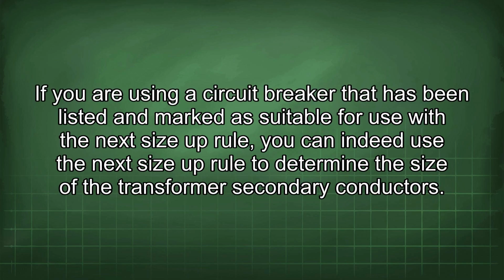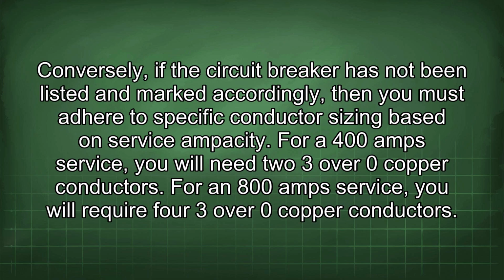If you are using a circuit breaker that has been listed and marked as suitable for use with the next size up rule, you can indeed use the next size up rule to determine the size of the transformer secondary conductors. Conversely, if the circuit breaker has not been listed and marked accordingly, then you must adhere to specific conductor sizing based on service ampacity. For a 400 amp service, you will need two 3/0 copper conductors. For an 800 amp service, you will require four 3/0 copper conductors.